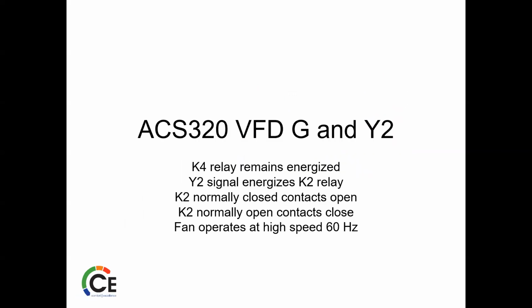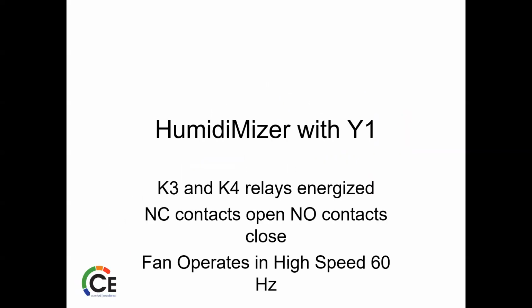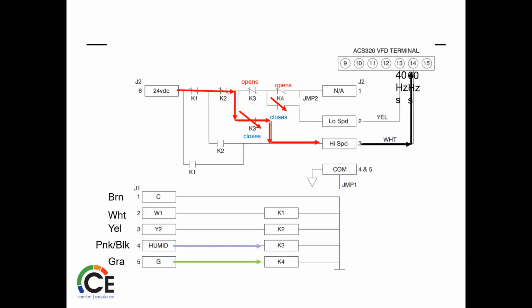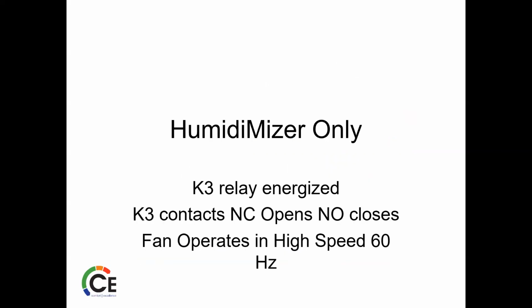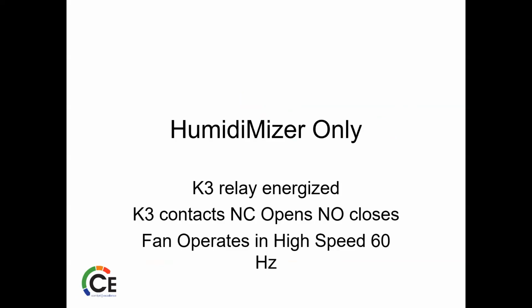So we get a G and a Y1. Again, open the upper relay, close the lower one, because we've energized it. Now we get a 40 hertz or 66% fan. And of course, Y2 we talked about, so that's going to be high speed. Now we got high speed fan because we have a Y2 call. HumidiMizer in Y1, same thing. You get high speed. Even though it's a Y1, because we have the humidizer activated, we're getting high speed fan. HumidiMizer only, same thing, high speed fan.